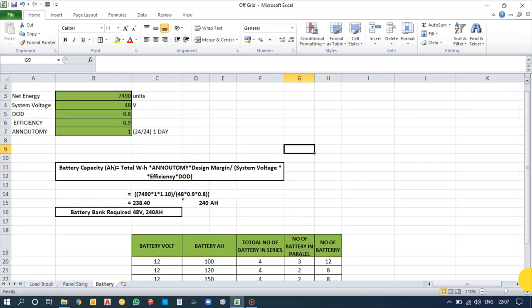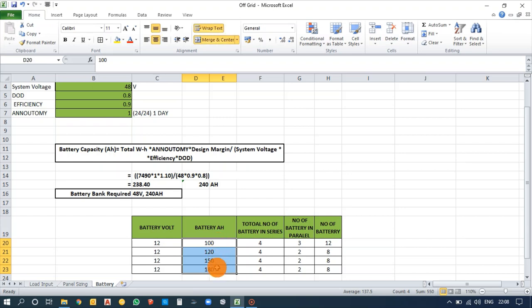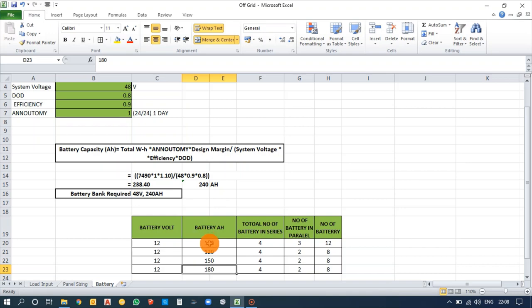For battery selection, I have selected 12-volt batteries, which are commonly used. They are available in 100, 120, 150, and 180 Ah formats. To achieve a 48-volt system, you need to connect four 12V batteries in series. The number of parallel connections depends on the Ah of the battery to meet the total Ah requirement.